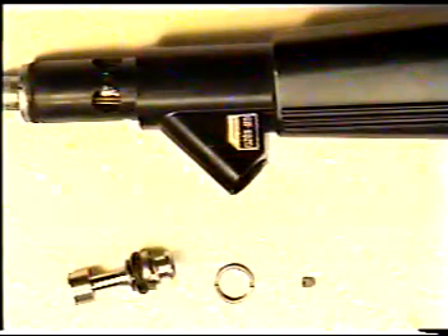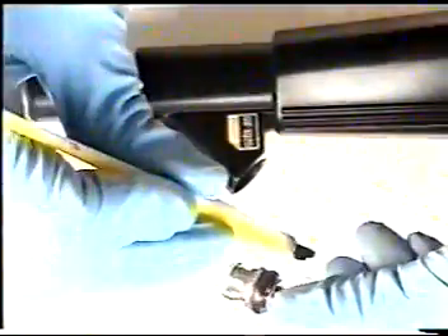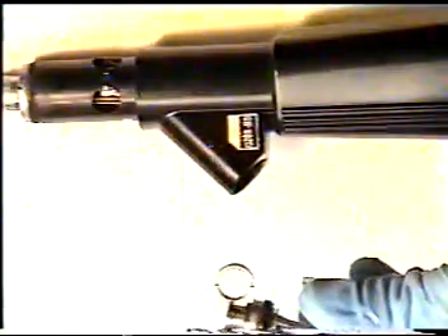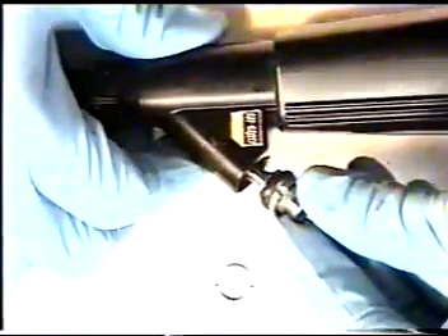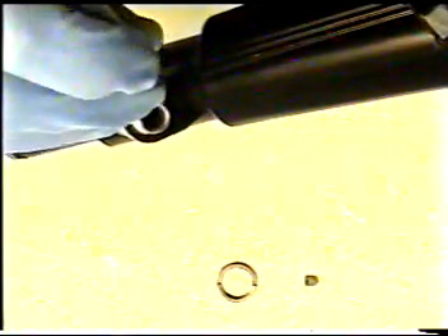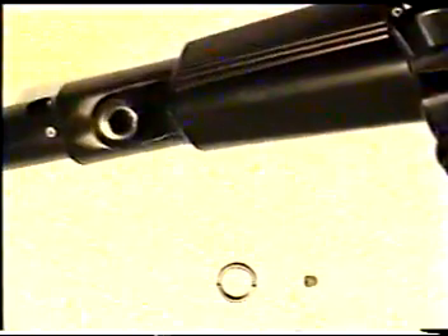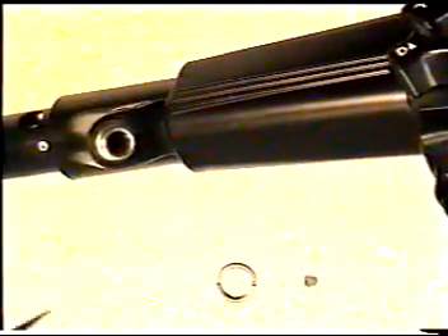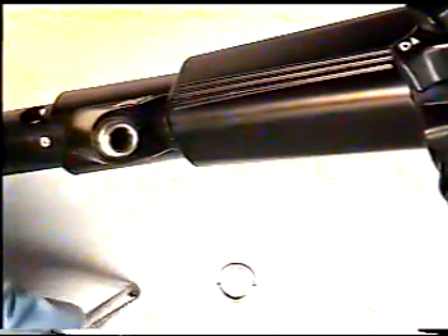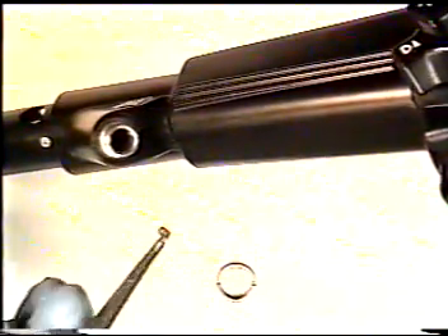We'll now replace the biopsy port assembly. First, we will take the biopsy port, cleaning off the O-ring with white lithium grease, which will allow for a proper seal. Slide the body housing at a 90-degree angle towards you with the slot at 90 degrees. Then, using tweezers, slide the port to meet the notch in the body housing. Retain the key for the biopsy port, sliding it into the notch at the top.